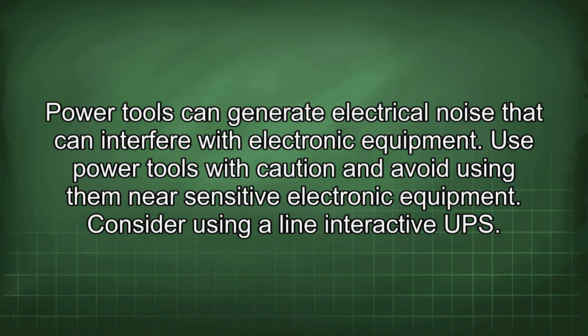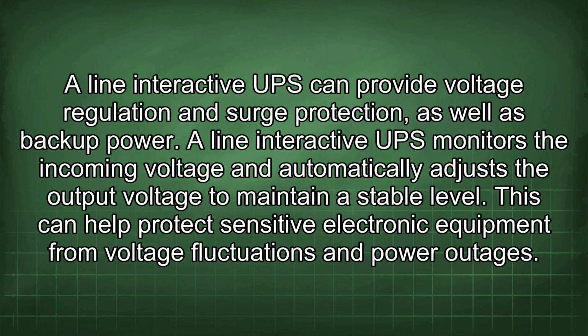Consider using a line interactive UPS. A line interactive UPS can provide voltage regulation and surge protection, as well as backup power. A line interactive UPS monitors the incoming voltage and automatically adjusts the output voltage to maintain a stable level. This can help protect sensitive electronic equipment from voltage fluctuations and power outages.